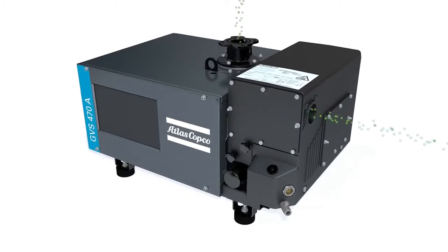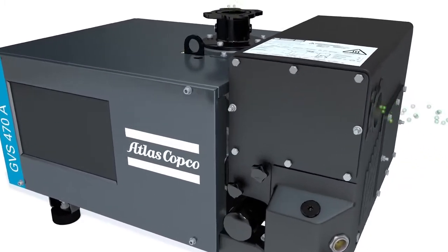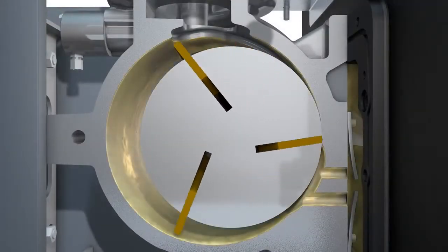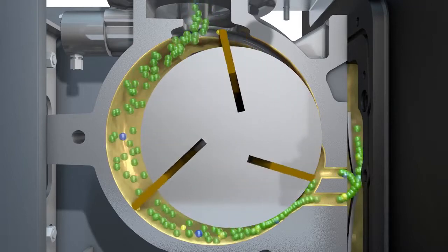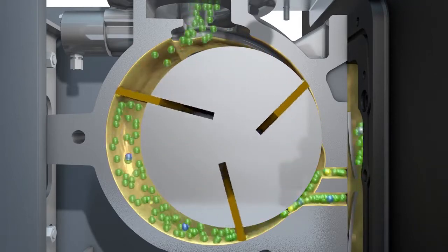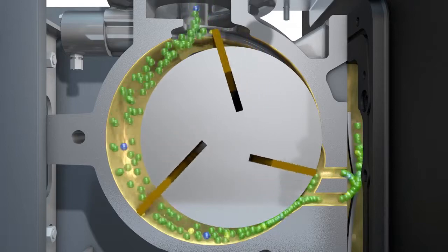As the rotor starts spinning, centrifugal force makes the vane slide to the outside and seal against the stator housing. A volume of process gas gets drawn in through the inlet valve as the rotor turns. This volume is then isolated from the process side and the exhaust.